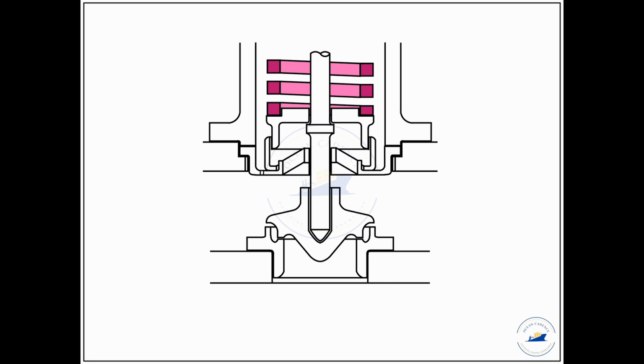Also, a general hand test in the form of a drop test is carried out, where the spring is dropped onto a flat surface from a certain height, and the rebound, that is the bounce, is observed to make sure that the spring still has elasticity and has not been damaged due to inoperation or steam damage that has occurred.